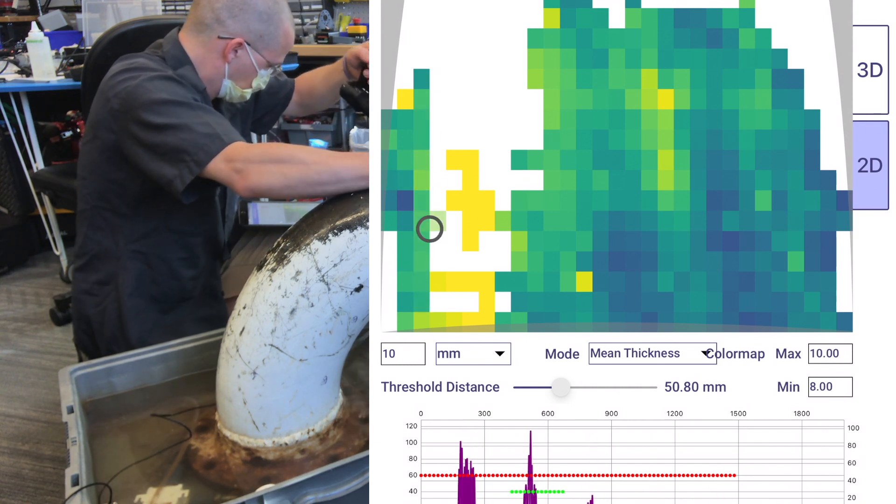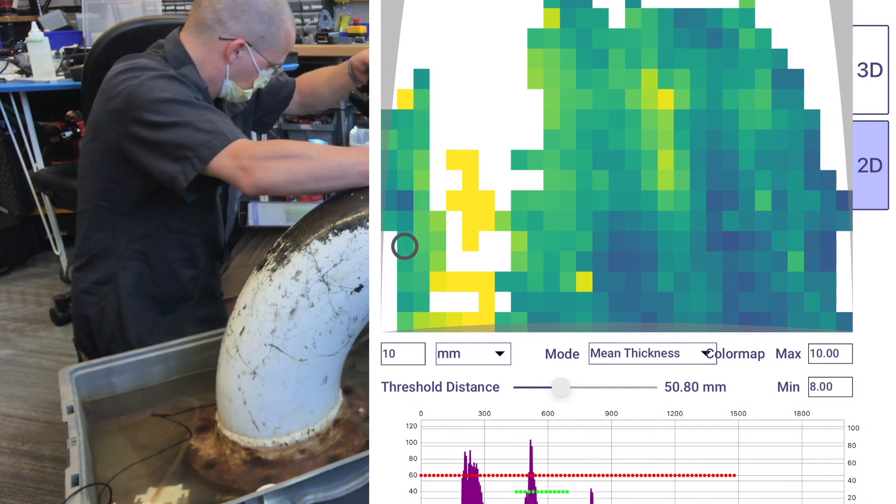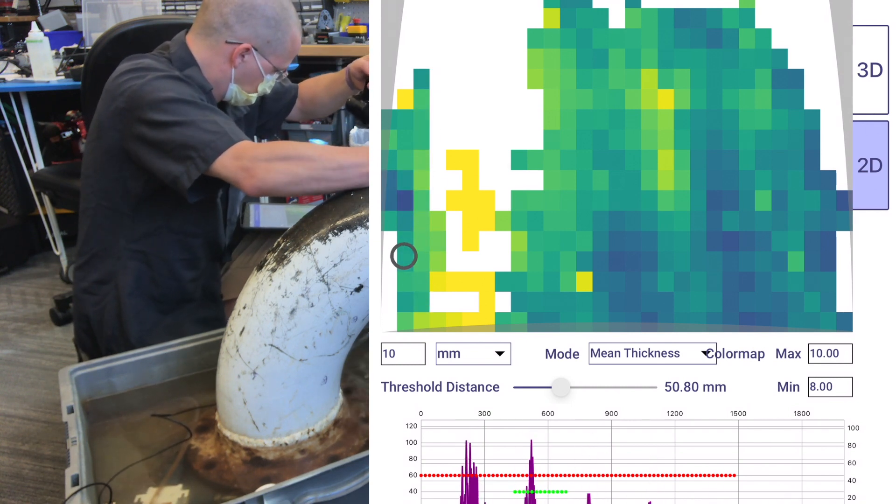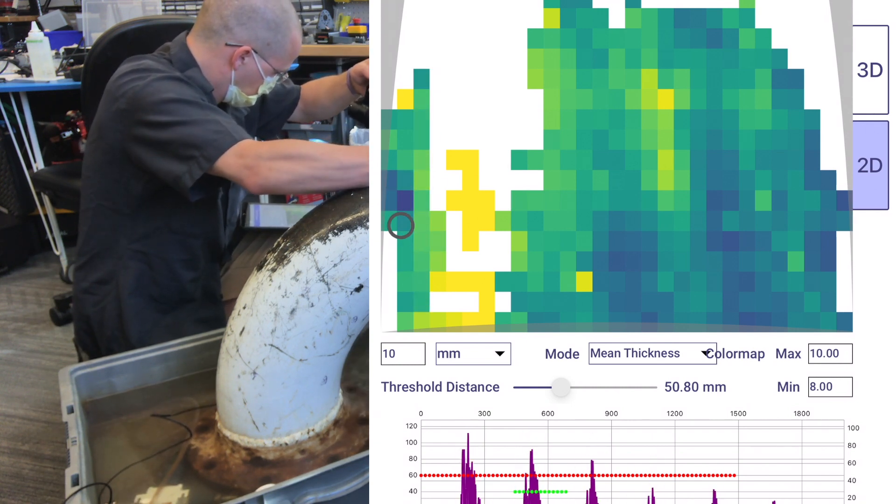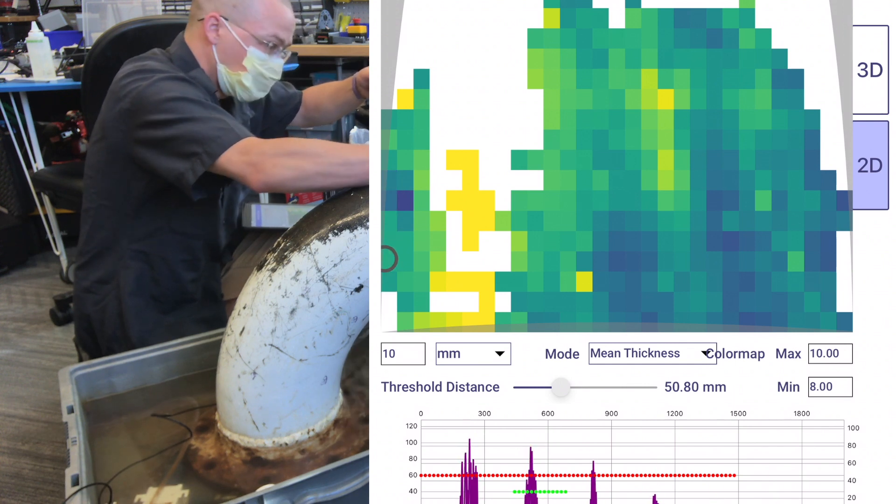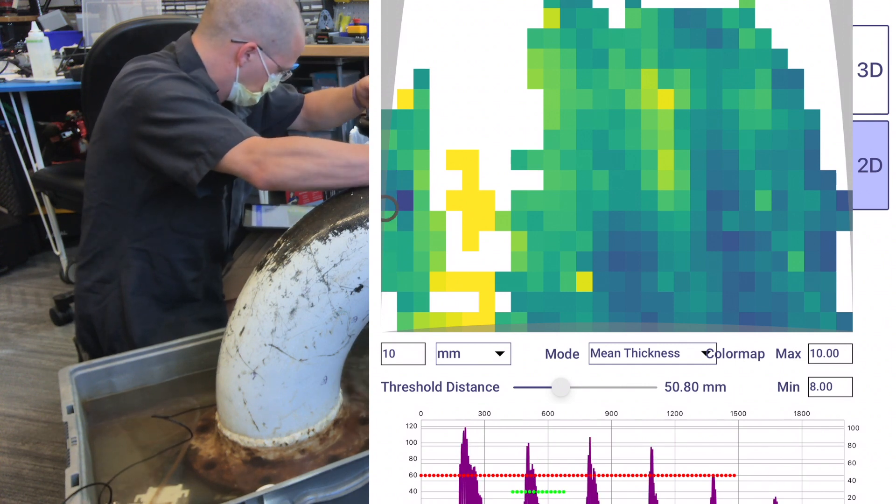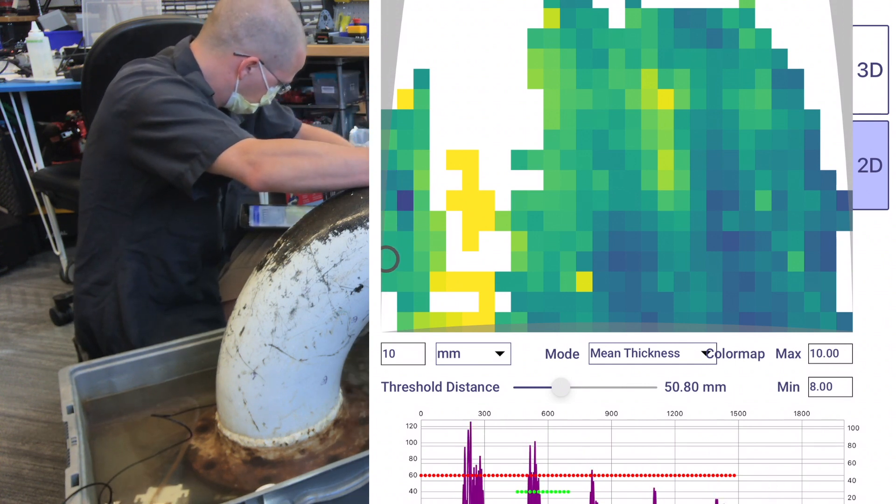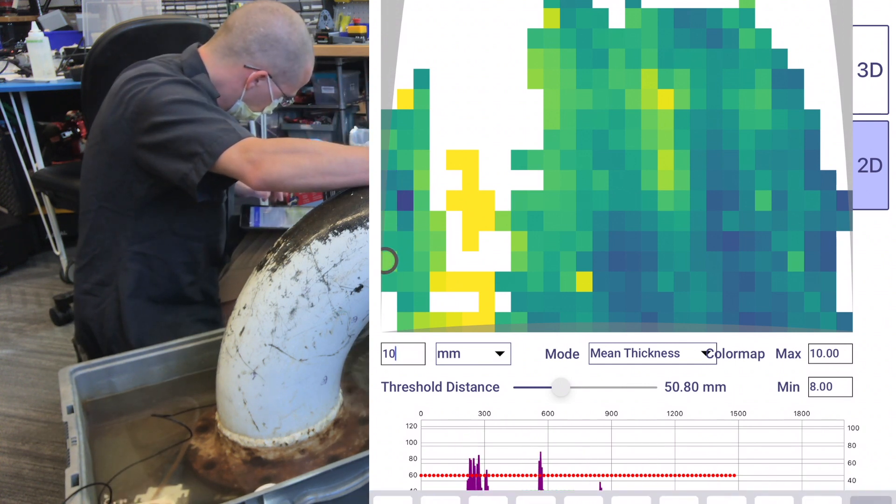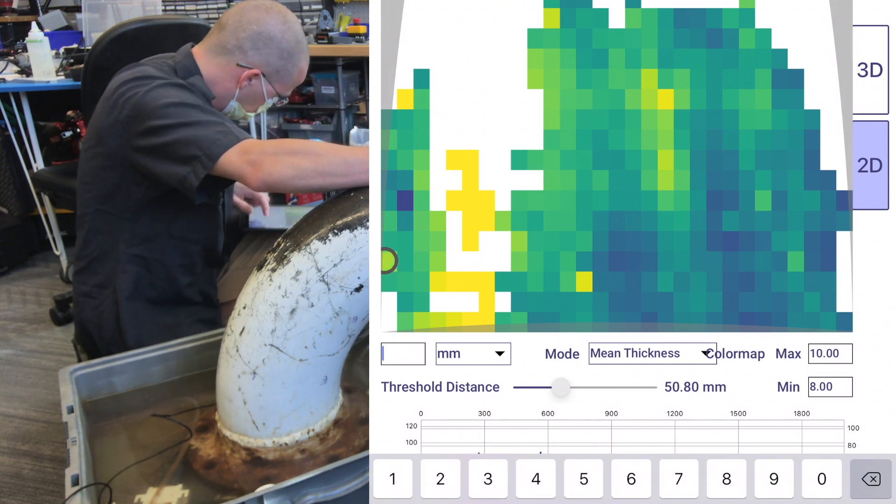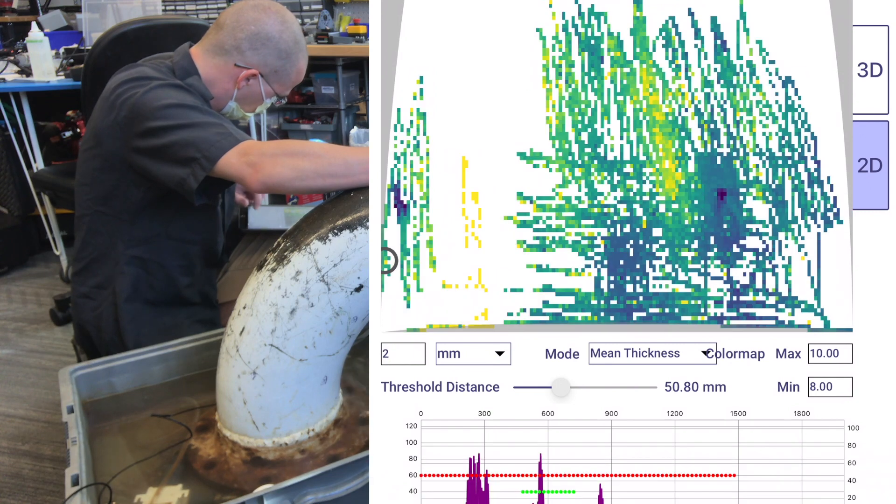On the other side of that weld, we've now found another spot that looks like a thin spot. Now I can go and I can decrease the grid size. This time I'll go to 2 millimeters.